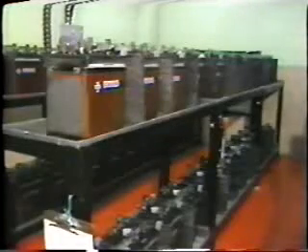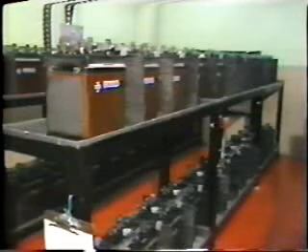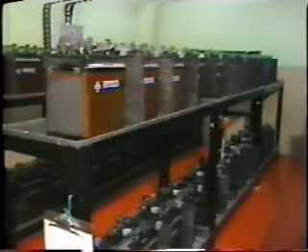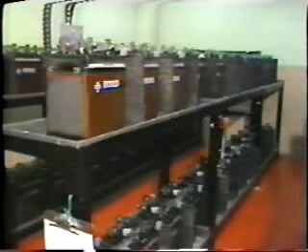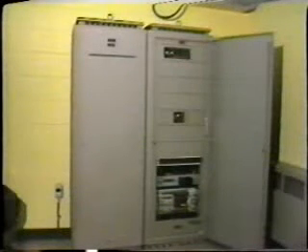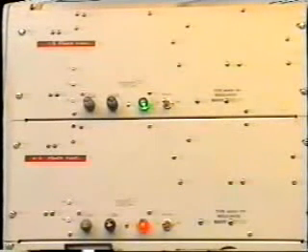First, the power supply. The carrier equipment is usually operated from the station battery, say 125 volts. Other arrangements exist where a 250 or 48 volt battery is used. There is also a PLC power supply available that will run off 120 volts AC. This requires the installation of an inverter so that the carrier can continue to operate from the battery during power outages. The power pack in the carrier provides the special voltages for the carrier electronics.